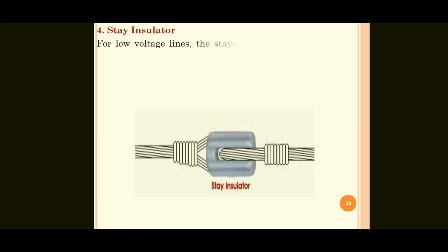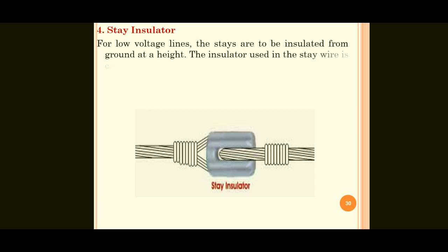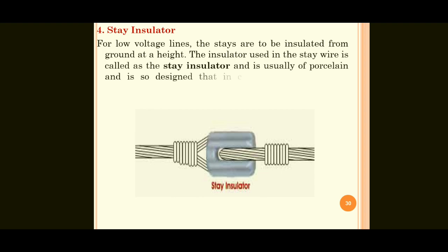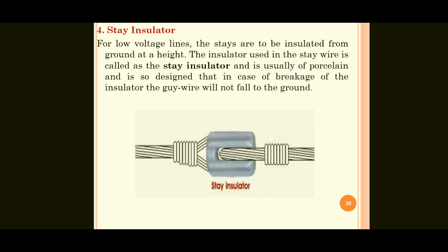Next one, stay insulator. For low voltage lines, the stays are to be insulated from ground at a height. So here stay insulators are used in low voltage ratings. The insulator used in the stay wire is called the stay insulator. Stay means stand still. It is usually of porcelain and is so designed that in case of breakage of the insulator, the guy wire will not fall to the ground. So for low voltage levels, the stay insulator is used. This figure shows the stay insulator.